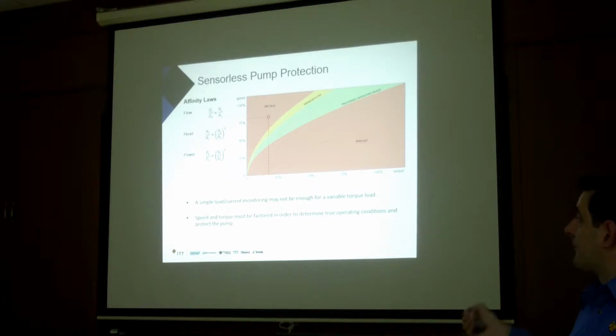So here we map where the acceptable pump operating region is for every torque and every speed. Whereas a regular variable speed drive, maybe they use 50% torque. So when it's 50% torque, they will dry run. But you can see here that if you're at a lower speed, 50% torque is acceptable. So then the customer has a problem and they decide we need to lower that value. So then they lower the value to 25. So they can start operating here, between these two speeds. But the problem then is that sometimes you get a dry run and you could be at 50% torque.